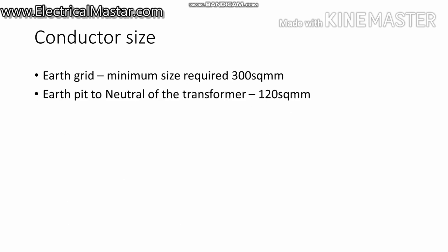And second, earth pit to neutral of the transformer. We know earthing is separate and grounding is separate. Grounding means the neutral of the transformer or generator connected to the earth pit. In my last video I already explained the difference between grounding and earthing. If you did not watch that video, I'll give the link in the description box. You can also click this eye icon to get that link. For this earth pit to transformer neutral, you have to use 120 square mm copper cable. This also has to be bare copper conductor.